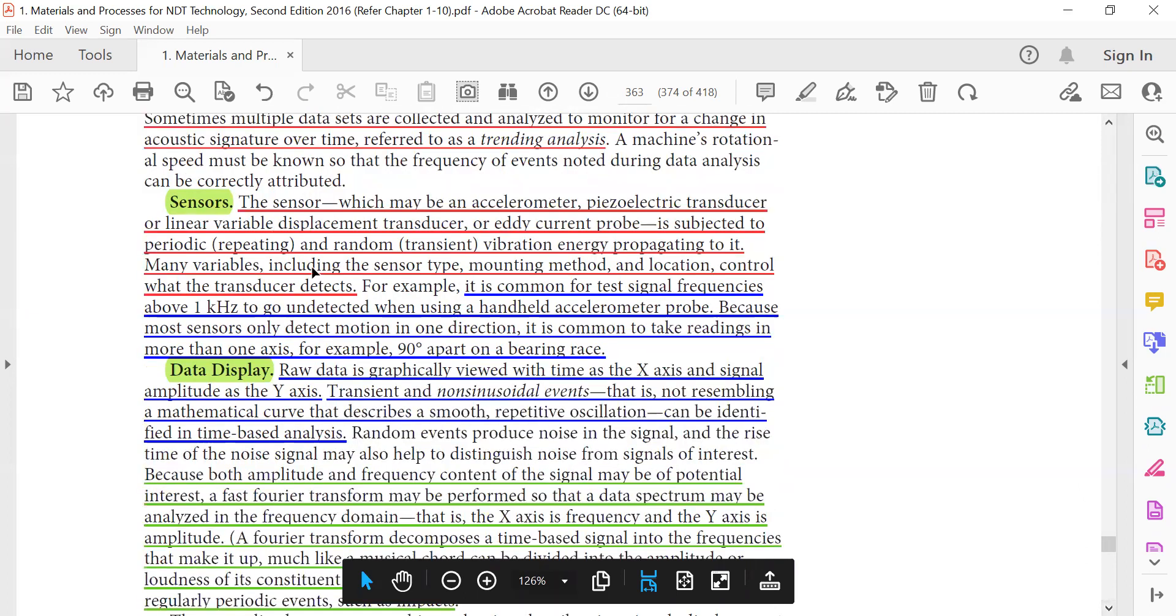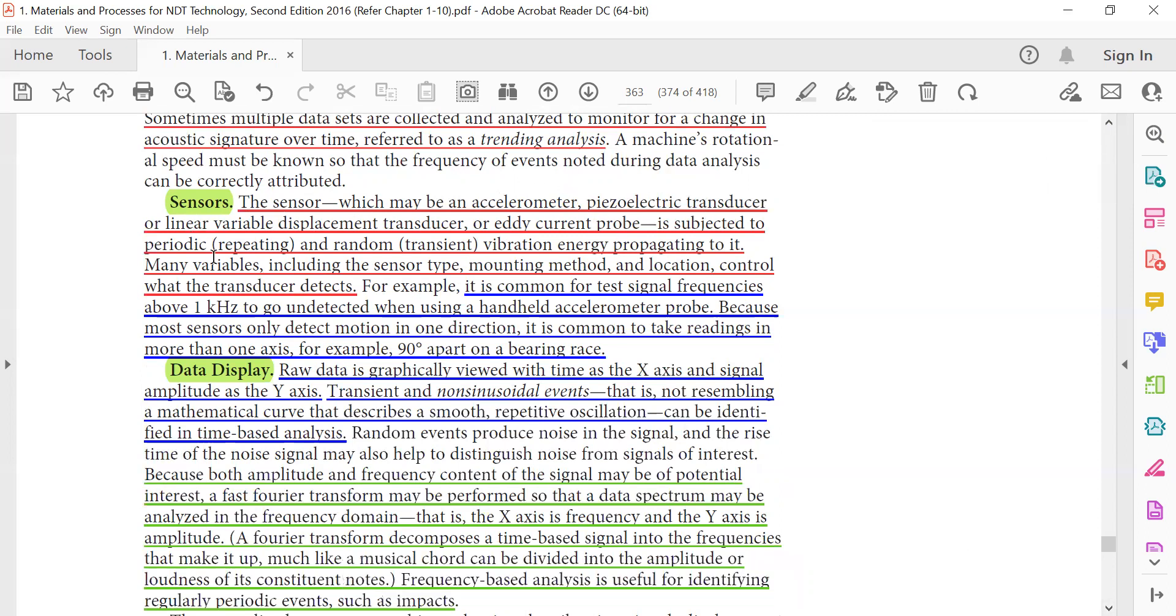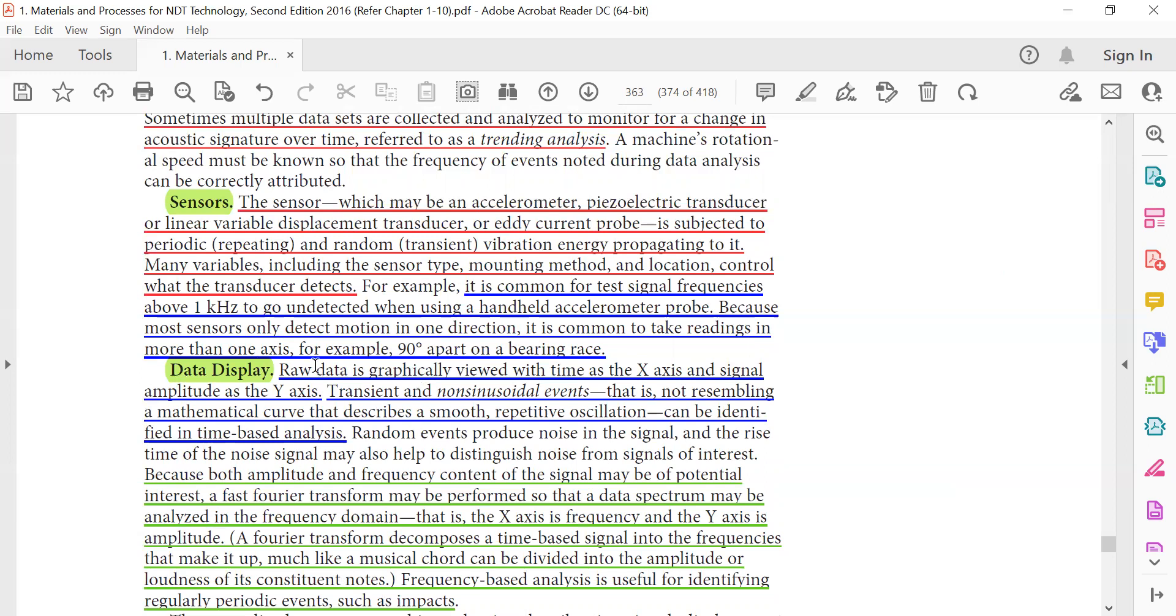Sensors: the sensors, which may be accelerometer, piezoelectric transducer, linear variable displacement transducer, or eddy current probe, are subjected to periodic repeating and random transient vibration energy propagating to it. Many variables including the sensor type, mounting method, and location control what the transducer detects. It is common for test signal frequencies above one kilohertz to go undetected when using a handheld accelerometer probe, because most sensors only detect motions in one direction. It is common to take readings in more than one axis, for example 90 degrees apart on a bearing race.